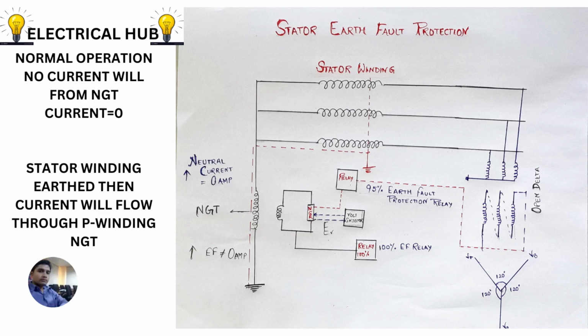So, what will happen during the normal operation of the generator? During the normal operation, no current will flow through the neutral. And as the current is zero, no current will be induced in the secondary winding, and there will be no voltage drop across the NGR.